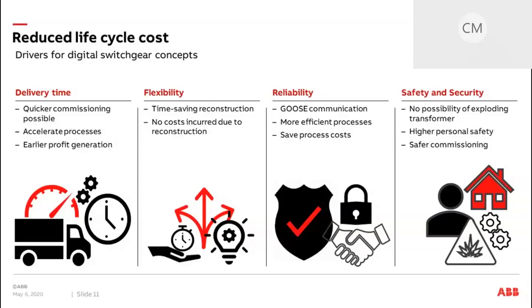Last but not least, a digital switchgear brings increased safety because you cannot incorrectly install a sensor as you can do with voltage transformers and then it blows up during commissioning. Also, less material is exposed to high voltage electrical stress, decreasing the risk of failure of the equipment.